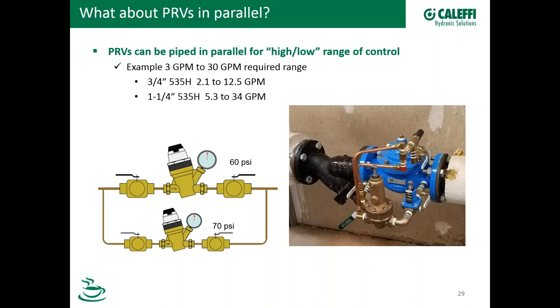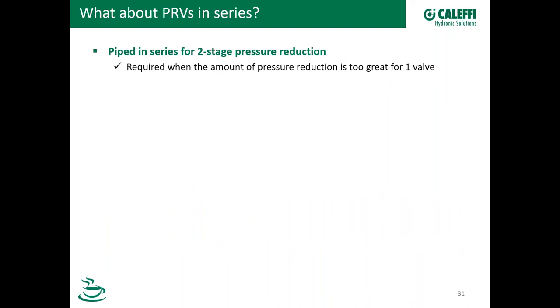What about PRVs in series? Yes, it's very common to pipe them in series for two-stage pressure reduction. When do we need to do this? If the amount of pressure reduction is too much for just one valve, we put two valves in series. Caleffi says 2-to-1 is ideal, and we have a soft guideline of up to 3-to-1. You may be able to go higher, maybe even up to 4-to-1, but the consideration is that at those high ratios you're looking at possible cavitation, noise, and erosion. For example, if you try to reduce 200 PSI to 45 PSI, no matter whose valve you have, you're probably going to have problems. We've heard recordings of valves literally screaming — a really high pitch that can break glass.